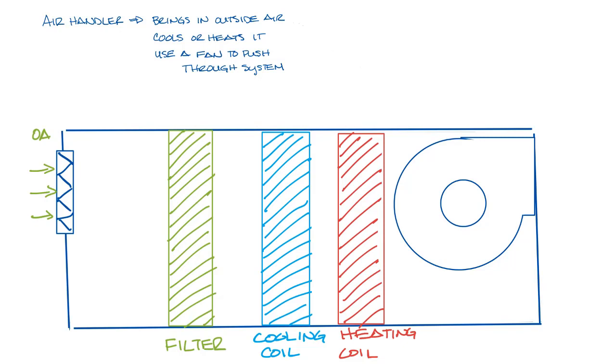Air handlers can have the fan before or after the coils. If the fan is before the coils, it's called blow-through arrangement because the air is blown through the coils. And if it is after the coils, it's called draw-through arrangement because the air is drawn through the coils. Draw-through units are more common than blow-through units, and we can talk about why in a future video.